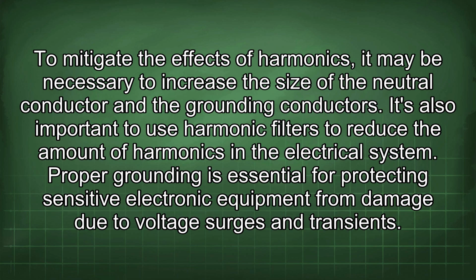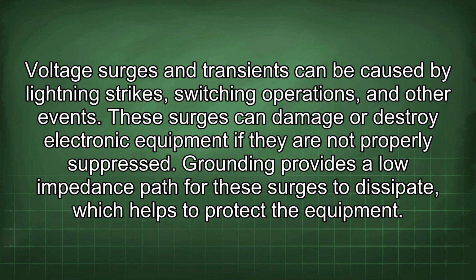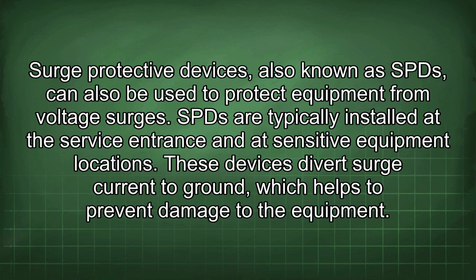Proper grounding is essential for protecting sensitive electronic equipment from damage due to voltage surges and transients. Voltage surges and transients can be caused by lightning strikes, switching operations, and other events. These surges can damage or destroy electronic equipment if they are not properly suppressed. Grounding provides a low impedance path for these surges to dissipate, which helps to protect the equipment. Surge protective devices, also known as SPD, can also be used to protect equipment from voltage surges. SPD are typically installed at the service entrance and at sensitive equipment locations. These devices divert surge current to ground, which helps to prevent damage to the equipment.